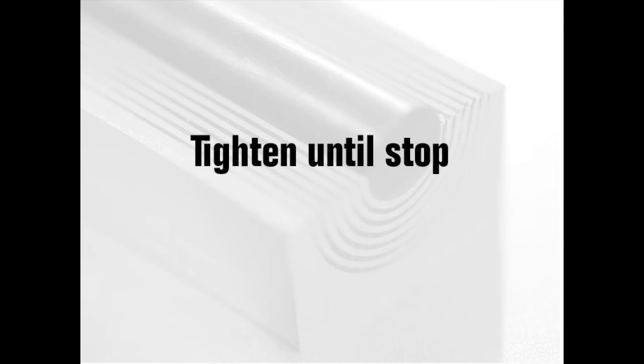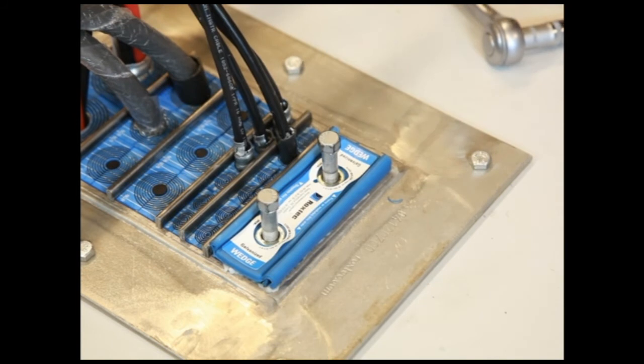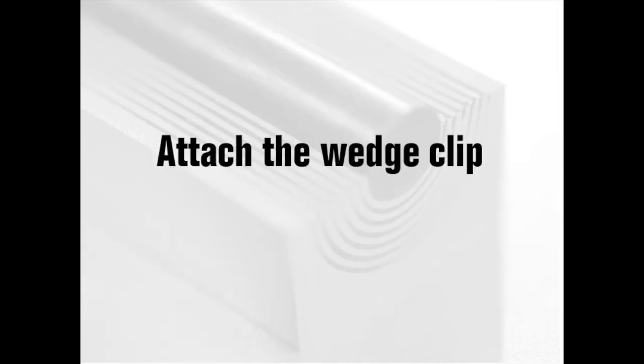Tighten the bolts alternately until stopped. The wedge will compress and seal the transit and the excess lubricant will be squeezed out. Attach the wedge clip to check that the wedge is properly tightened.